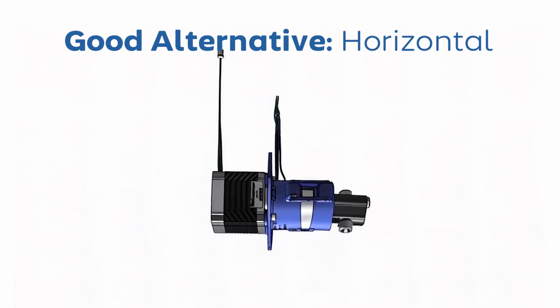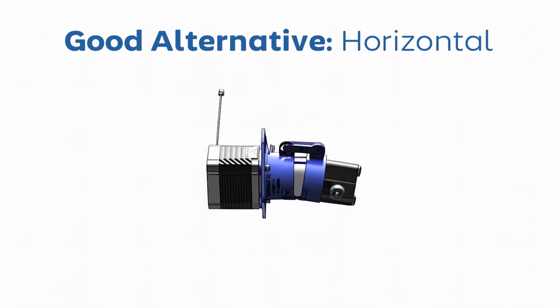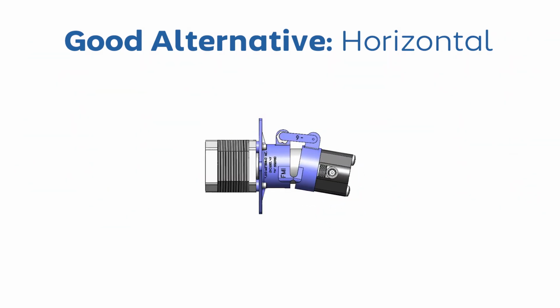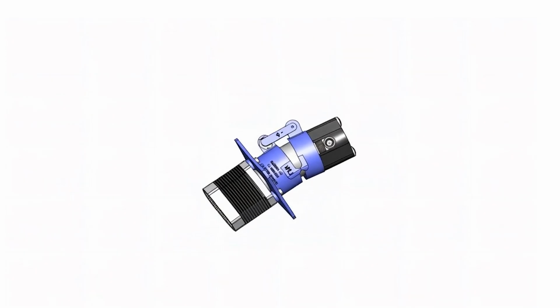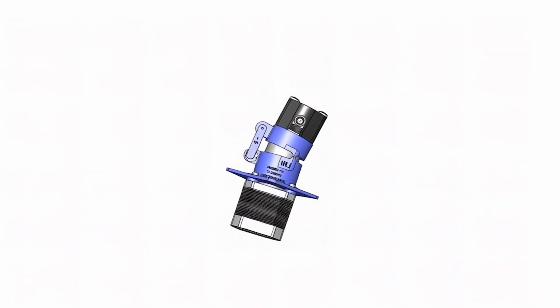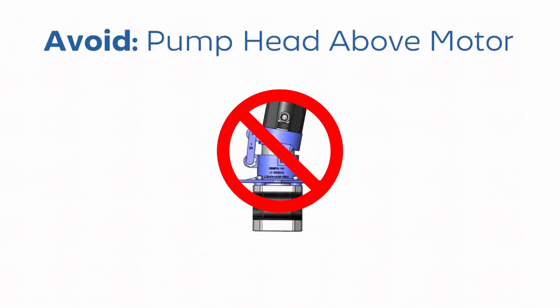A 45-degree rotation with the inlet and outlet aligned horizontally is another acceptable configuration. It offers similar benefits, but it's slightly less effective when it comes to pushing air out of the system. All of these mounting positions are acceptable and will give you strong performance. The one orientation you should avoid is having the pump head facing upward with the motor below it. In that position, air bubbles can become trapped inside the pump, which can affect precision and accuracy. Additionally, gravity will pull the fluid down towards the seals, increasing the risk of a leak over the life of the pump, possibly even allowing fluid to reach the electronics below.